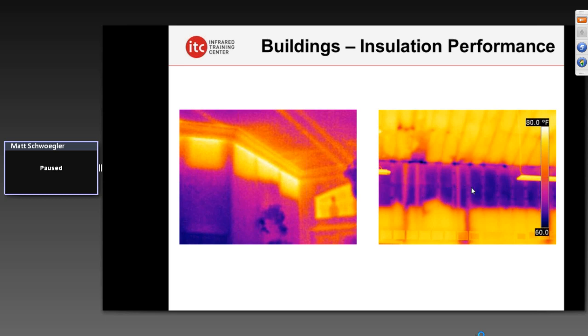In this case, some missing insulation in cold weather: we see the framing being a little warmer, the cavity a little cooler, indicating heat loss from inside to outside. In the warm-weather example on the left, the level of insulation on the wall shows up quite well. I want to stress that one of the limitations of thermal imaging is that we cannot see beneath the surface. We're relying on the surface patterns themselves to reveal subsurface thermal anomalies — we're seeing the effects of heat transfer showing up on the surface.